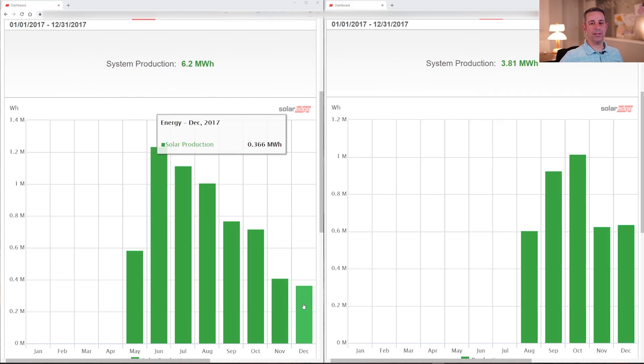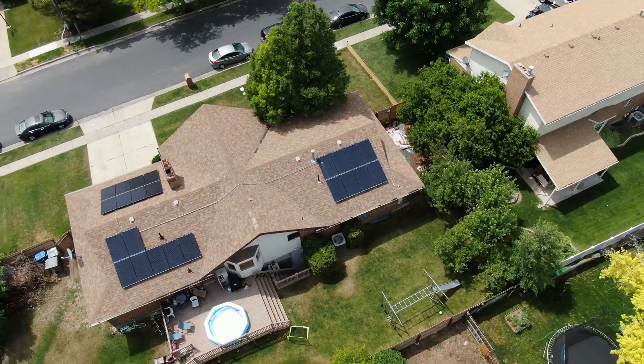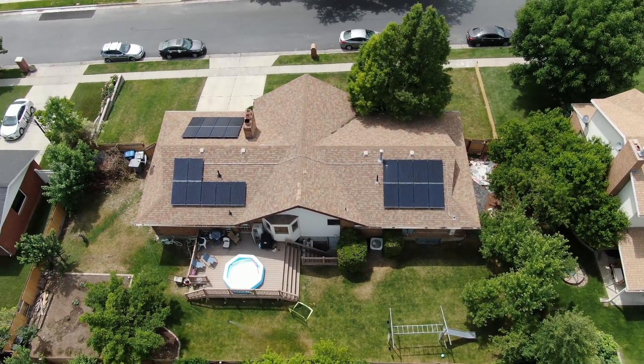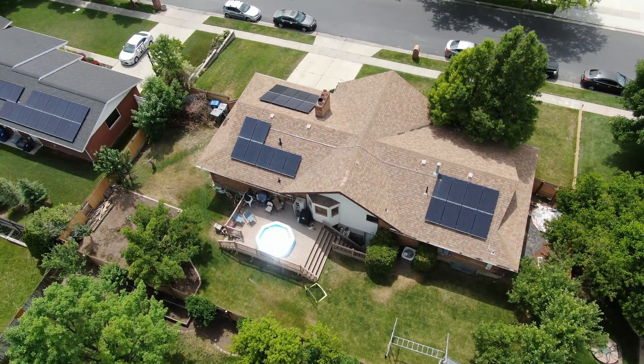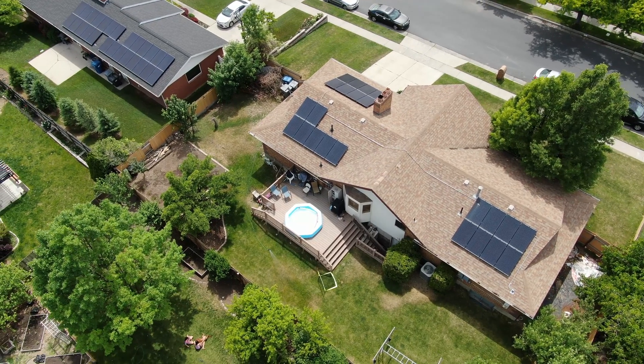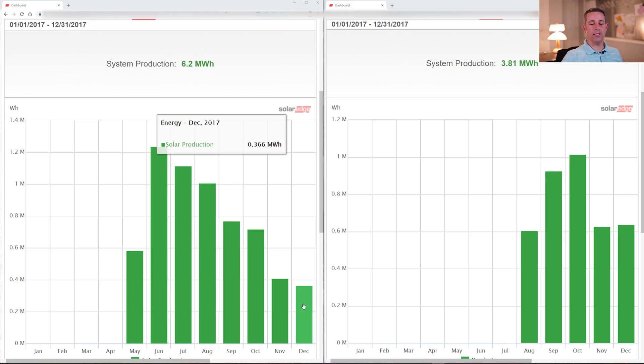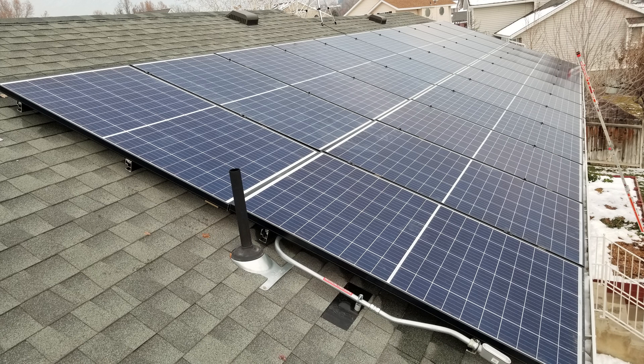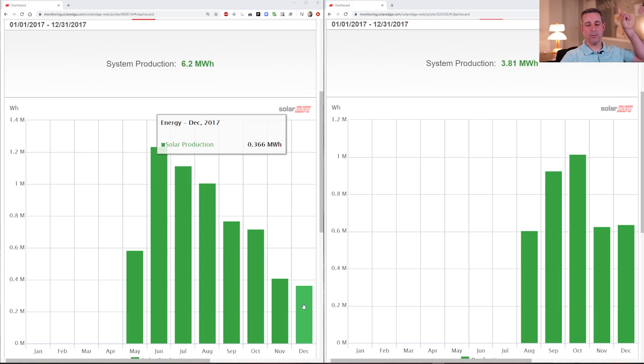Another reason why I think in winter their production is not quite as good is because of the orientation of their panels and their position on the roof. When it snows, the snow just slides off their panels a little bit and then builds up along the valley of the roof. My roof also had some of that same problem this winter, and it wasn't until the next summer that I shifted the panels closer to the edge of the roof so that the snow would go straight off the roof. I actually created a video about that. If you're interested, click on this card right here.